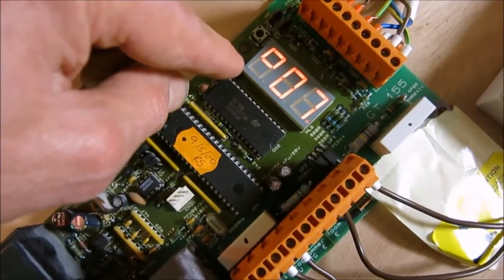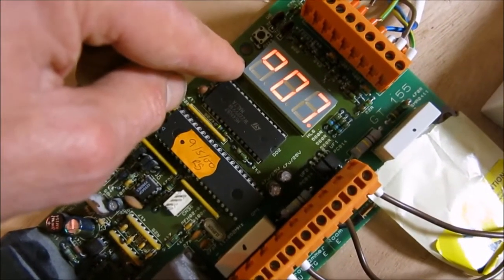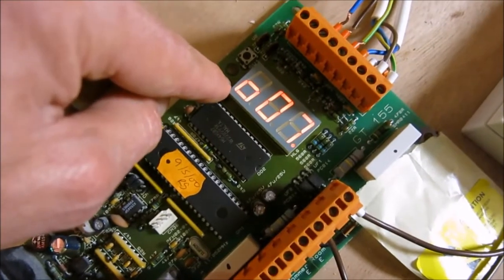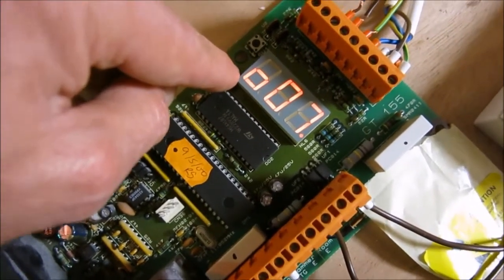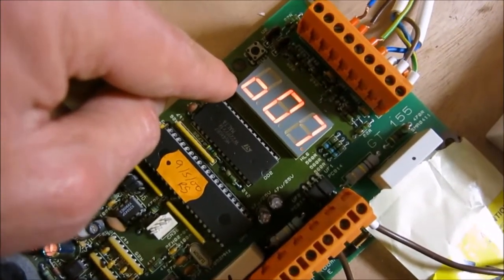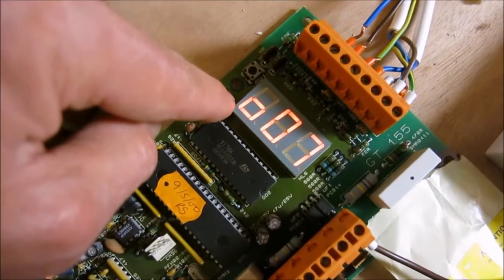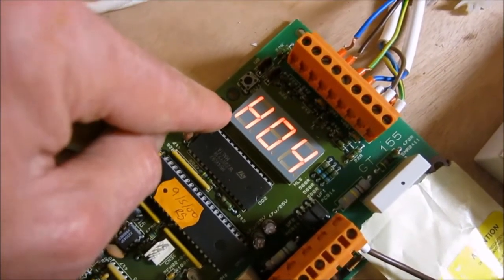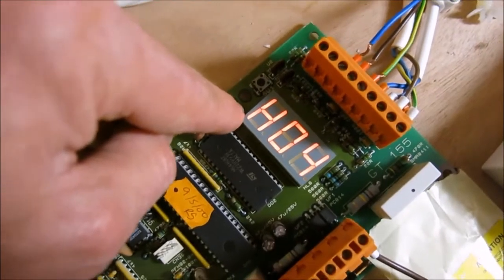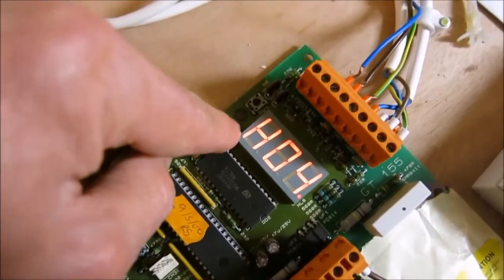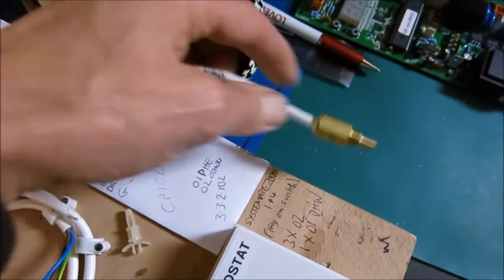You can press those. If you press SW2 first time, it shows you the temperature of the tank, the hot tank, the heat store. Next one shows you the direct hot water plate heat exchanger thermistor, the one at the top of the plate heat exchanger. The third one shows you the one at the bottom right of the can. It's the direct hot water return on the Boilermate 2000. These thermistors, by the way, are an electronic device. There's a chip in there that talks to this.